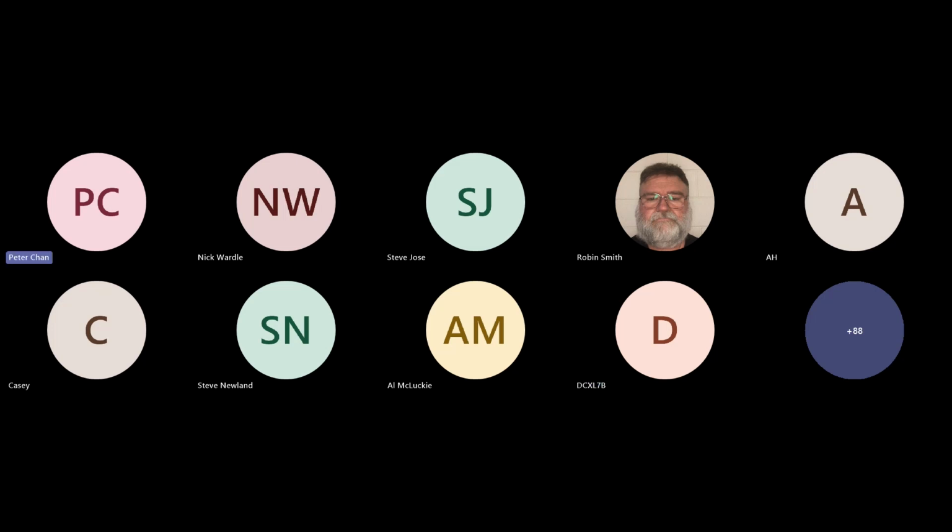Short answer. So Robin, can you just provide an outline as to what the authorisation is under the Act? So what do people need to do? Yeah, the Act simply says a person who conducts electrical work must complete a certificate of compliance that certifies the electrical work was tested and safe, and the electrical work complies with the Act. So if the person who conducts the electrical work is employed or engaged to carry out the work by the holder of an electrical contractor license that is not authorized to complete a certificate of compliance, the holder of the contractor license must complete the certificate instead of the person who conducts the electrical work. And of course, must be done within 20 days.